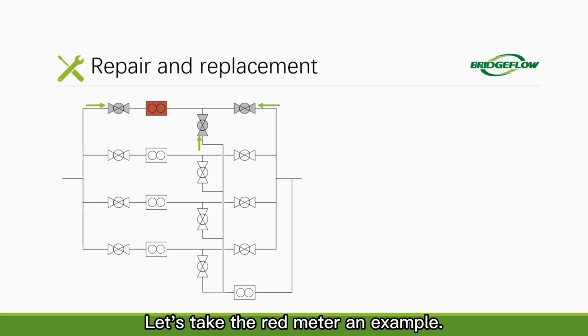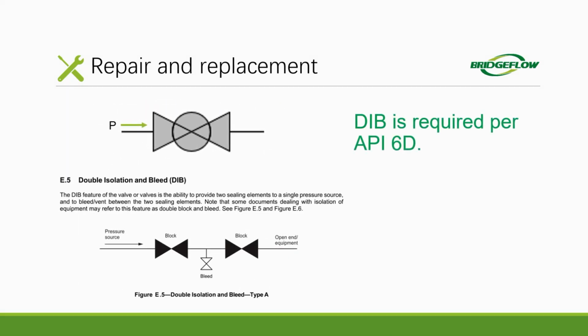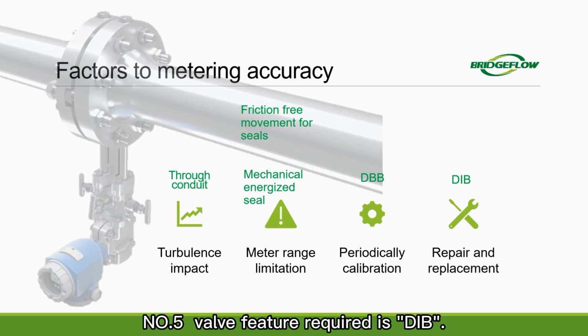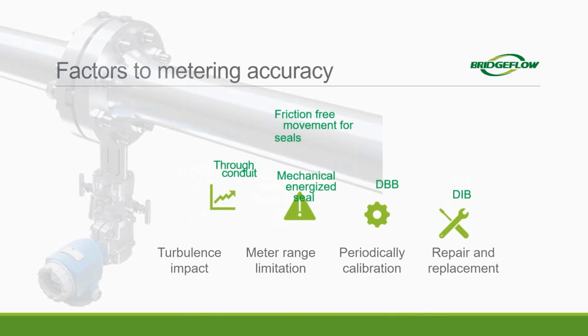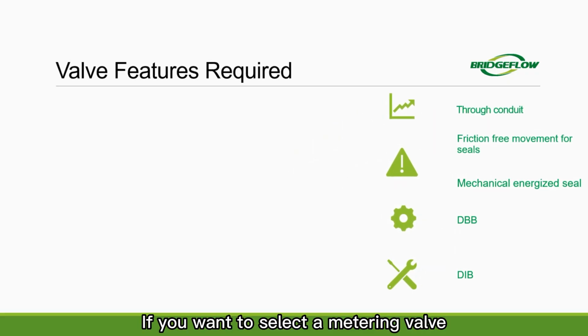Let's take the red meter as an example. To repair or replace this meter, 3 valves must provide proven isolation so that the red meter can be removed from its position. For flammable or explosive flow, such isolation must be positive isolation with proven zero leakage. It means that the valve must provide 2 sealings to meet DIB as per API 6D. Number 5. Valve feature required is DIB. If you want to select a metering valve that can fulfill your requirements, you need to consider all these features: through conduit design, friction-free movement for seals, mechanical energized seal, DBB, DIB.